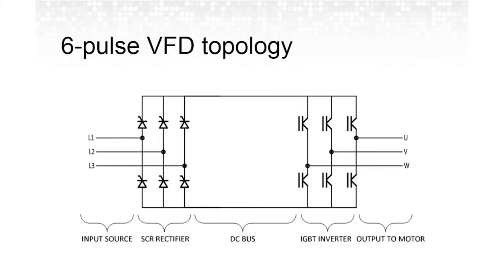While this diagram is a simplification, you can see that when we go on to the next slides, it is dramatically simpler than some other topologies that we'll talk about. And that leads us to why we would use a 6-pulse VFD. They're cheap, they're small, and they're efficient. Typically, most 6-pulse VFDs will be wall-mounted, and they can have much greater flexibility in where they're located. However, there is one really big drawback to this particular design, the 6-pulse design, and that drawback is harmonic distortion. They create dirty power.